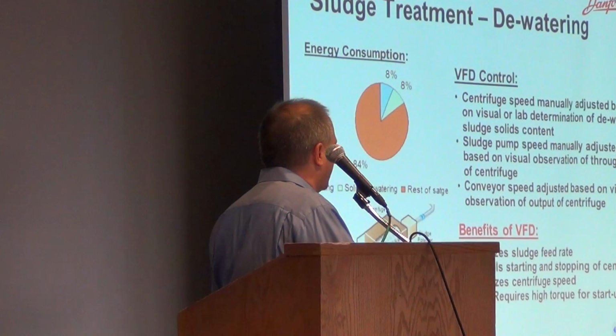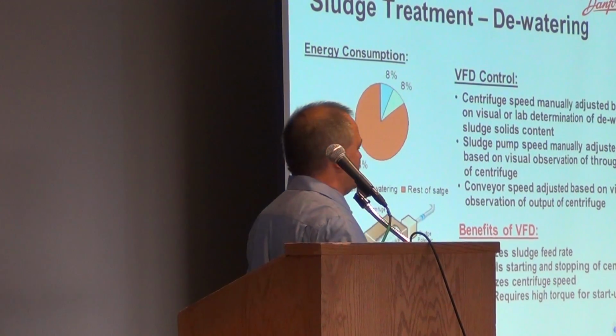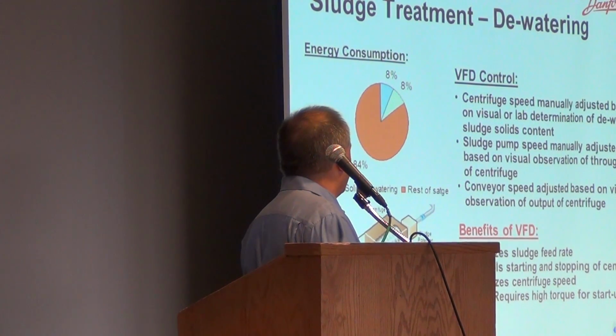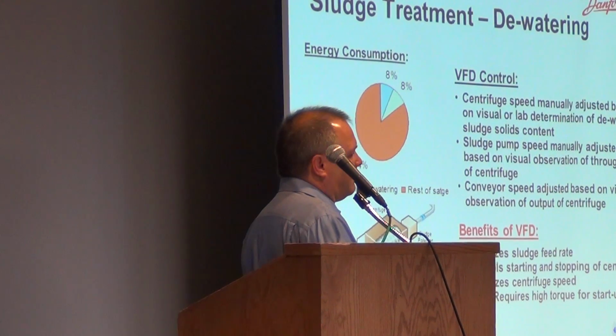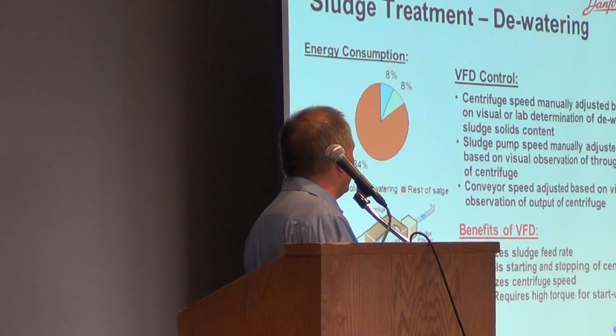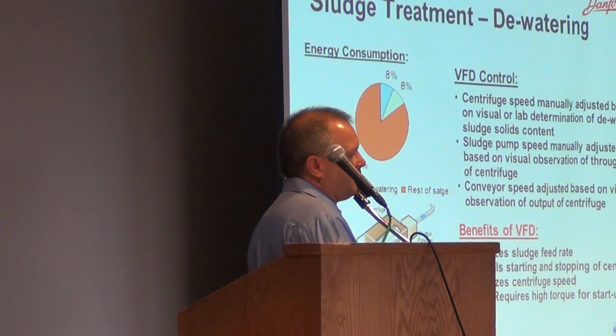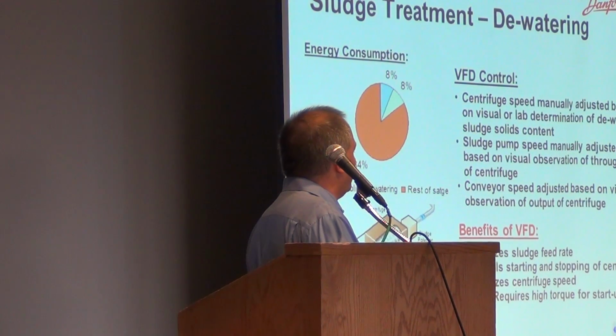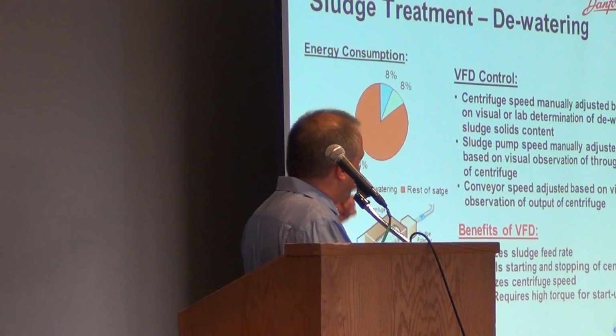On a centrifuge, the nice thing about a drive on a centrifuge is you're not getting that hard snap. It's a lot easier on the motor. You can get the centrifuge up to speed. You save a lot more on the wear and tear of the motor and the bearings in the centrifuge than you do conserving energy. Usually you're running your centrifuge at full speed. The drive can give us the high torque it needs to start, and then give us a nice ramp up.